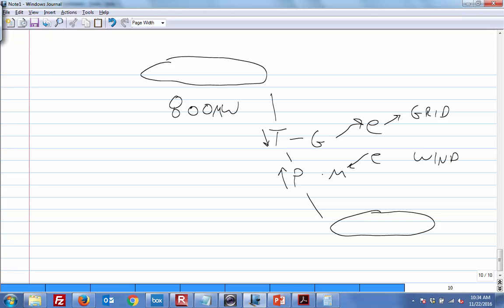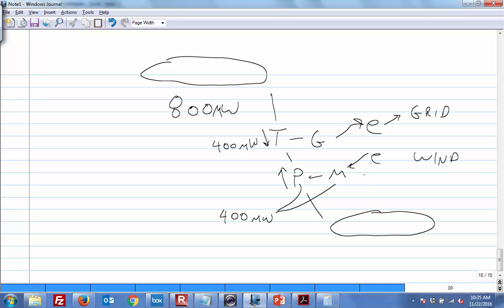The point is, the pumps sending water uphill, the turbine is allowing it to go downhill, the generator sends electricity out to the grid, and the motor powers the pump. So you have those four distinct technologies. And they work in tandem in such a way, the pump motor combination is 400 megawatts. And the turbine generator system is also 400 megawatts. So it can pump and generate at the same time, but you're never going to get out more than 400 megawatts. So the point is, it can make electricity as fast as it's coming in, but no faster. The whole point is, you don't want to ever overflow the system.